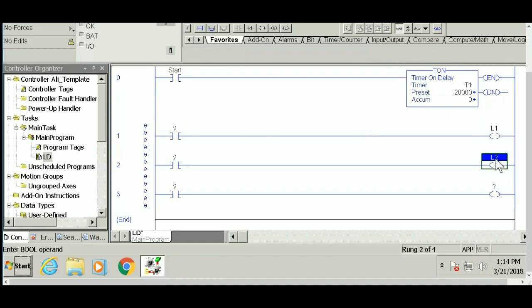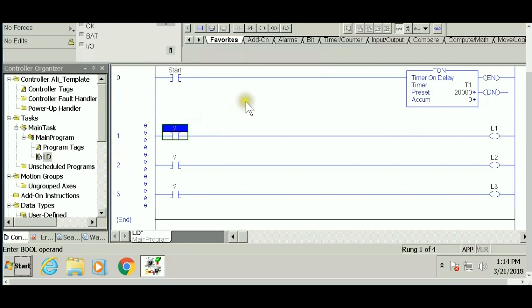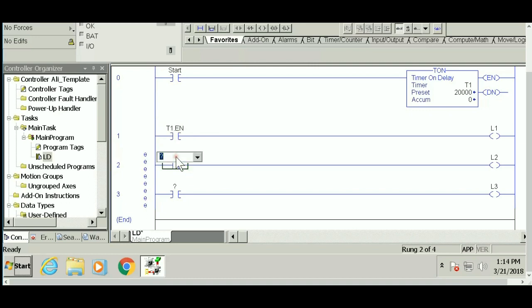Each output will be driven by one of the timer's boolean parameters. The syntax is timer name, so T1 dot the parameter. EN is the first one for enable. The second is timer timing TT. If you forgot the timer name, double-click the question mark, click the down arrow, and it takes you to the tags you created.